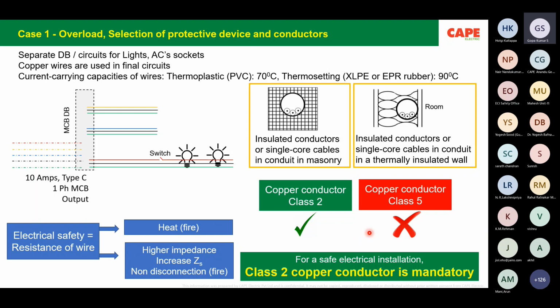In the market, in several places in India, class 2 copper wires are not available across the counter. If you want them, you have to be an expert and wait a few weeks to get this material. This situation is not correct. The standard considered only class 2 copper conductor in all the calculations. Instead of class 2 copper conductor, if you use class 5 conductor, number one, it is illegal. Your installation is not conforming to the National Electrical Code.